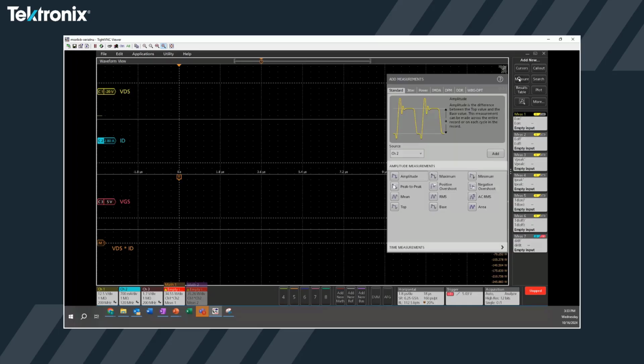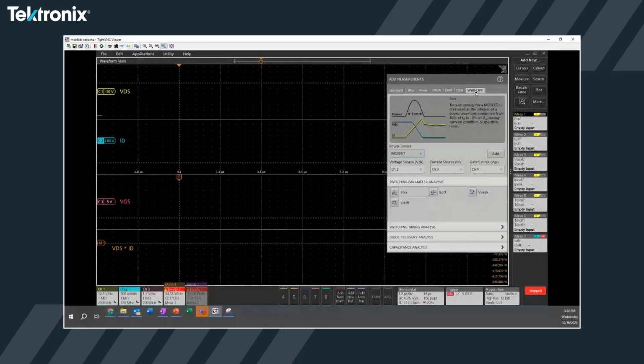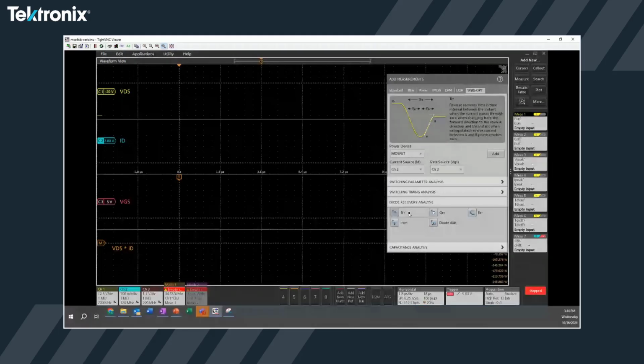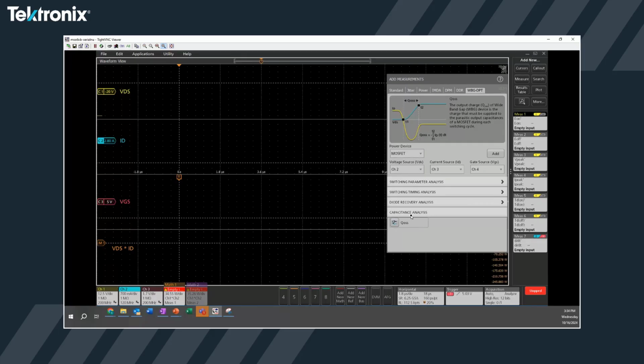To set up this measurement, we go into our measurement analysis tool and select wide bandgap double pulse test, a software option available for our oscilloscope specifically for double pulse testing. Here you'll see a wide variety of measurements from our switching parameter analysis, capturing energy on, energy off, V peak and I peak; switching timing analysis giving time to turn on and turn off, as well as dV/dt and dI/dt; and diode reverse recovery analysis, showing the time to recover from reverse recovery current, the dissipated charge, and the reverse recovery softness factor.